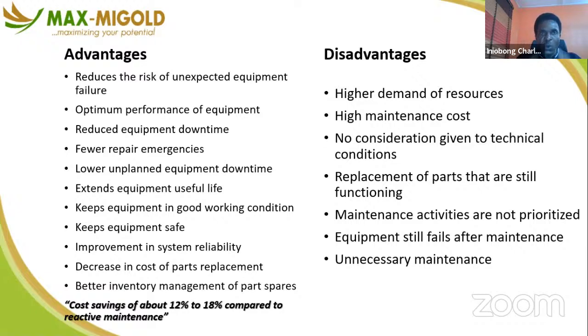It's too much, so what they do is that their generator, even though they don't use it since they rely on the turbine, they carry out an availability check on that generator every week. They will just turn on the generator and it will run for hours without even putting load on it, just to make sure that in case the turbine fails and power from the national grid fails, the generator will be reliable. So some organizations go to that extent to ensure their assets are very reliable and function once they are needed.